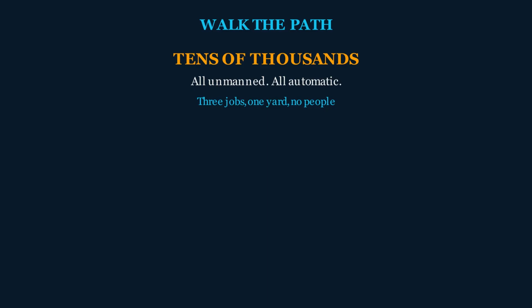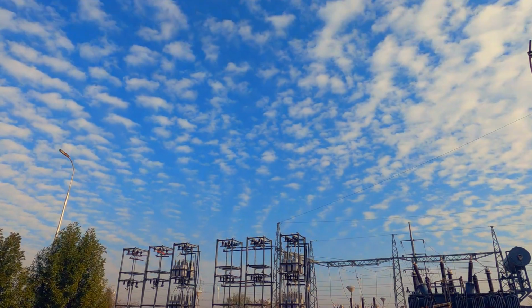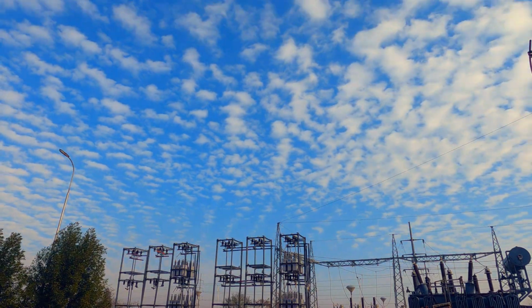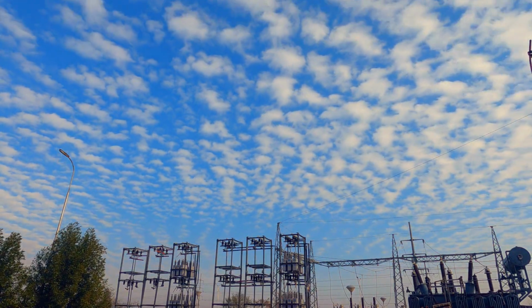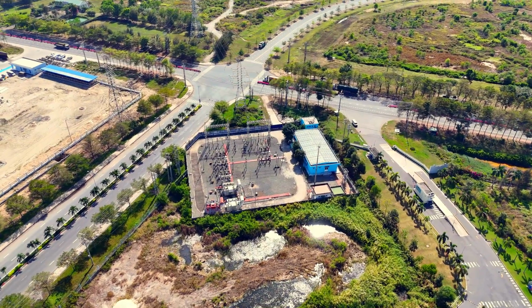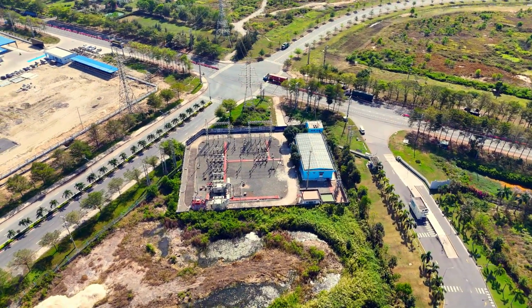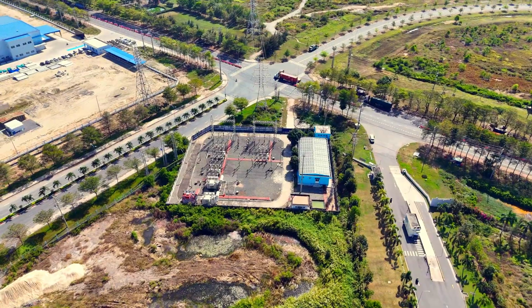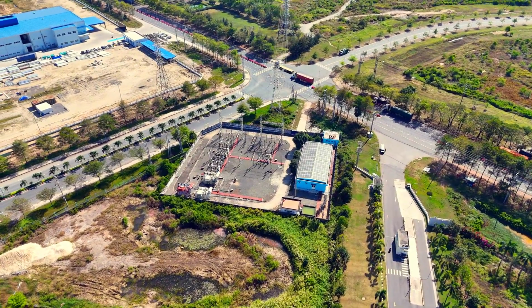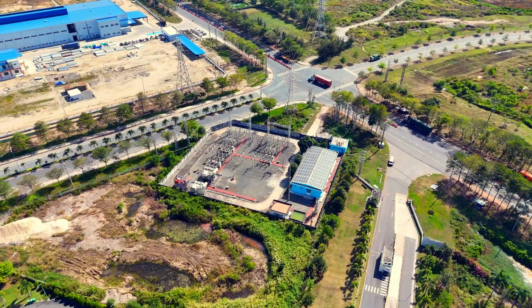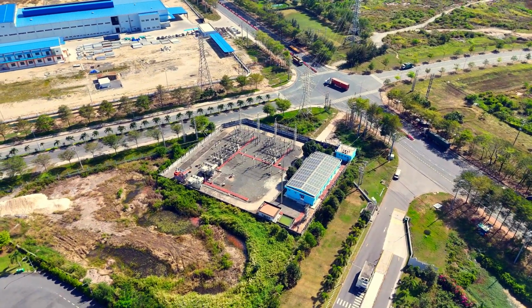The humming gray boxes change the voltage. The bars and breakers route and protect the power. The little building thinks. Three jobs, one yard, no people. So the next time you drive past that fenced-off lot of steel and insulators, you'll know exactly what you're looking at. The interchange where the interstate of the grid slows down to become the road you live on, protecting itself thousands of times a day without a single person on site.